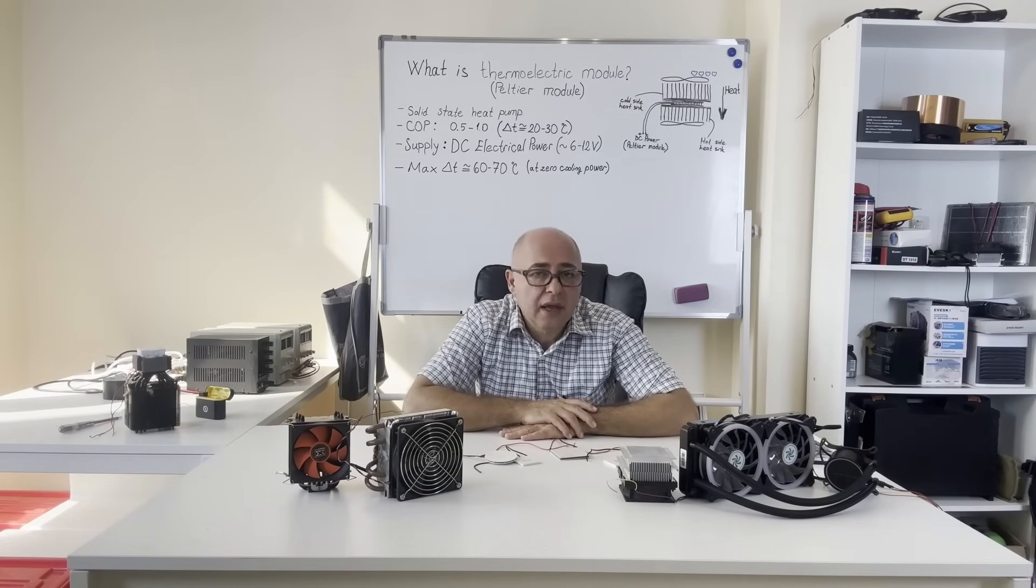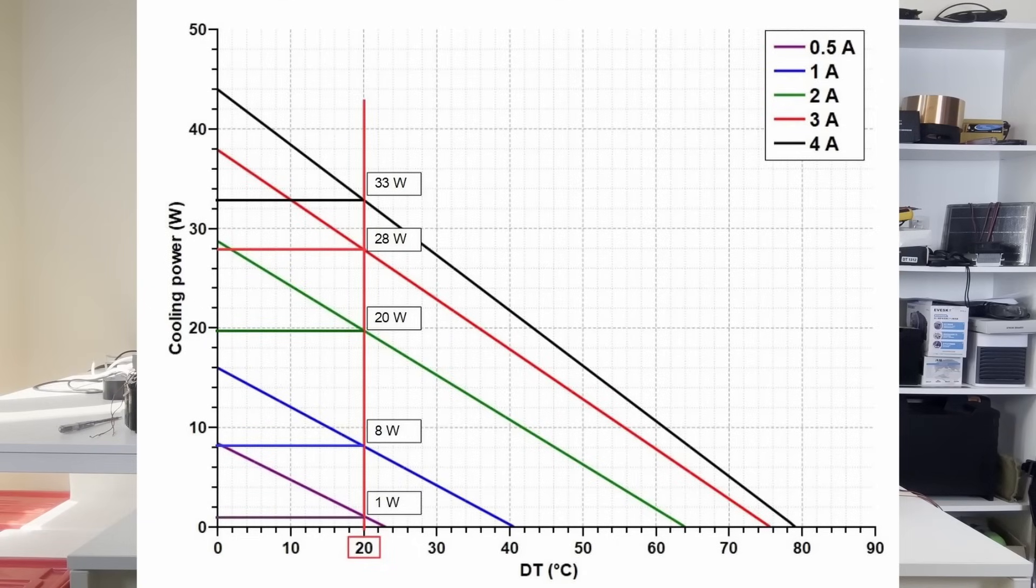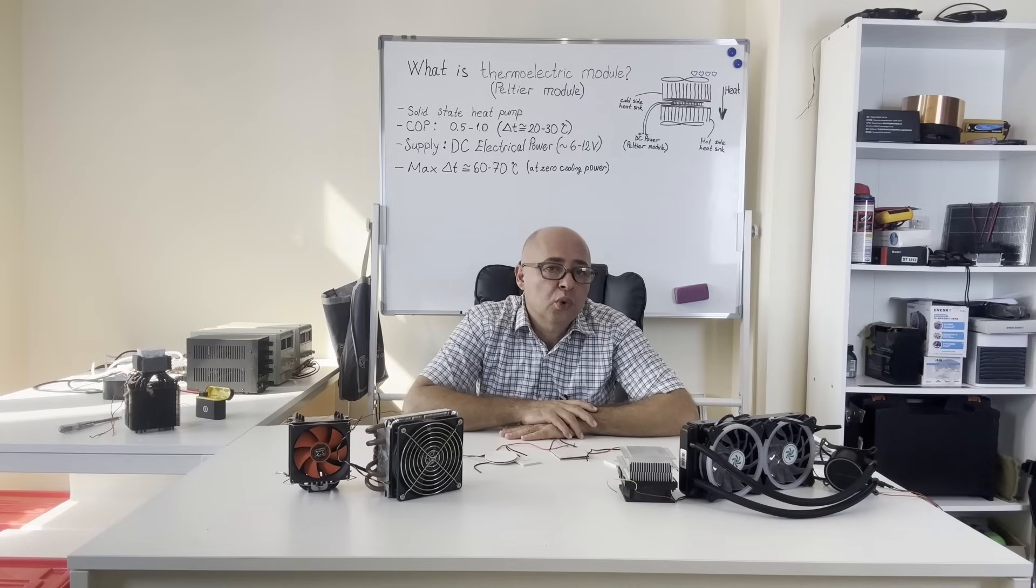you will see that as the temperature difference increases, the cooling capacity decreases dramatically. In practice, you can consider half of the catalog value for the cooling applications for 30 degree Celsius temperature difference.